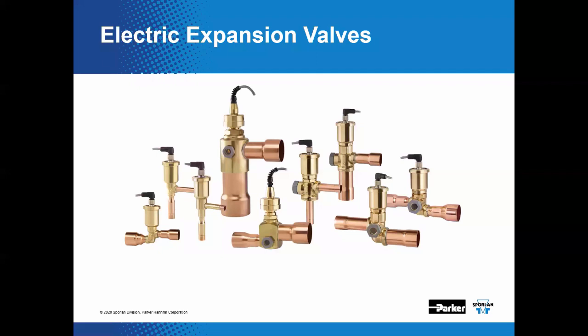Glenn, why would we do that? Well, Jim, it's one way of being able to see what's going on with the valve operation. And then it also has a moisture indicator in there. If you actually take a look, there's a ring of yellow. Like right there? Yeah, a ring of yellow right inside that window. And that yellow is the moisture indicator, same as in the Sporlan See-All. So it will change to green when the system is dried down by the filter dryer upon operation.